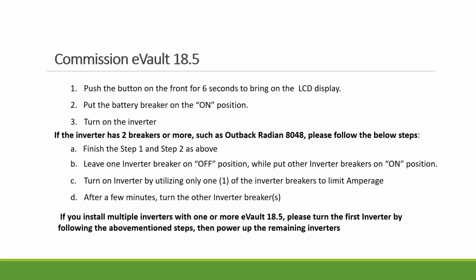With the eVault, we are using the button in the front to turn the BMS on and off. So the first thing you want to do is push the button to activate the BMS, and then there's a breaker, turn on the breaker, and then turn on the inverters. If you do this with the Radian, the same, you do step 1, step 2, but then you turn on 1 breaker first and let it rest a little bit, and then turn the second breaker on, for the same reason that we just discussed.